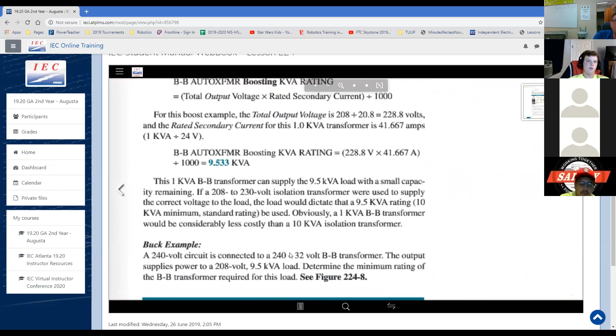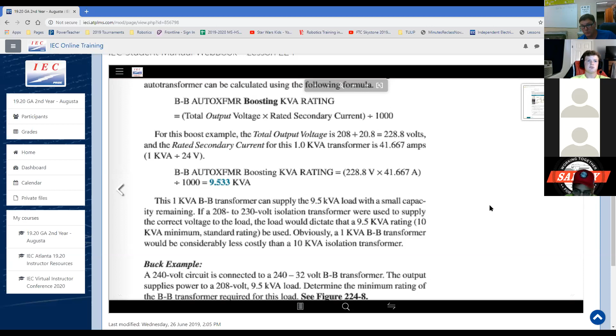This 1 kVA buck boost transformer can supply a 9.5 kVA load with a small capacity remaining needed. And so instead of buying a much more expensive 10 kVA isolation transformer, I can get away with that 1 kVA buck boost and that 9.5 kVA transformer. It's cheaper. That's why. That's the whole point of even doing this stuff.